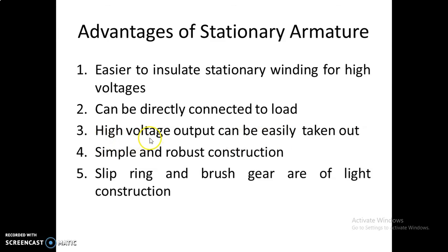The third advantage is that the high voltage output can be directly taken out from the stationary armature. Next, the construction is very simple and robust. The slip ring and brush gear used are of light construction. These are the advantages of using a stationary armature.